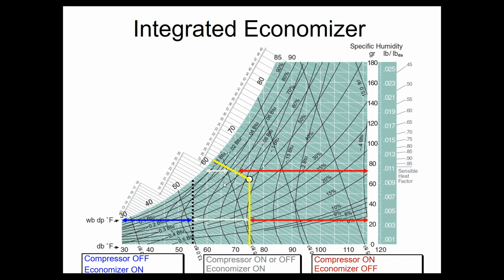Paul asks, AC equipment IEER rating based on equipment. IEER ratings are based on standard ratings. 80, 67, and 95 are not actual design conditions. The ratings are based on 80, 67 return air, meaning 80 dry bulb, 67 wet bulb, and 95 degree outside air. It has nothing to do with the actual conditions at your property, right? Because the ratings are for the equipment itself with no idea where the equipment's going to eventually go.